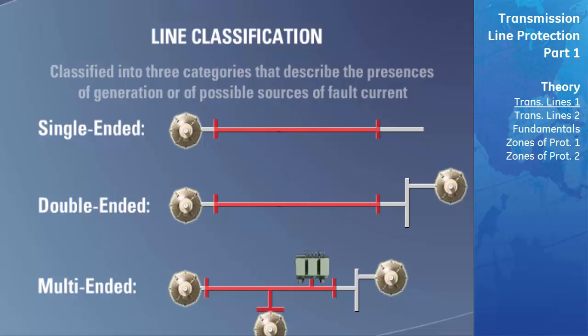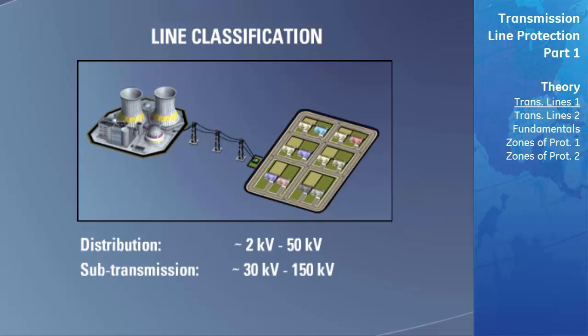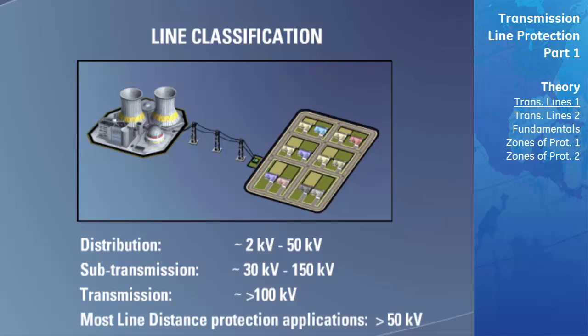The voltages used for transmission of power over transmission lines are split into three categories. These are distribution levels, which are in the range of 2 kilovolts to 50 kilovolts; sub-transmission levels, which are in the range of 30 kilovolts to 150 kilovolts; and transmission levels which are greater than 100 kilovolts. Most applications that use distance protection are 50 kilovolts or greater.